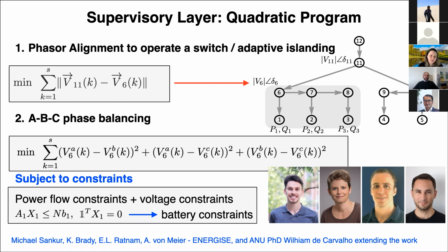So we have the same issue, and the US also has that issue of balancing. One particular strategy we're looking at with this phasor-based control is how to balance the grid out, and by balancing it we could improve the efficiency of the operation of the grid so we could avoid expansion. So it sounds like that's fairly universal across all the members here—we could have unbalanced networks with single, two-phase or three-phase connections. In this new paradigm, the supervisory layer could assign voltage phases to balance out the phase across A, B, and C, balancing out the power flow.